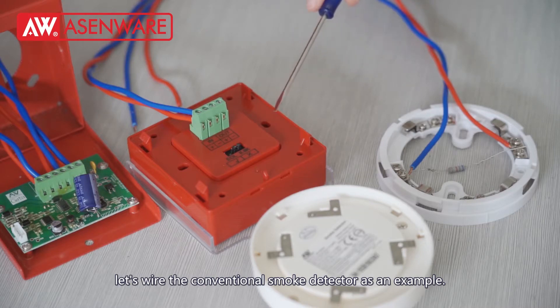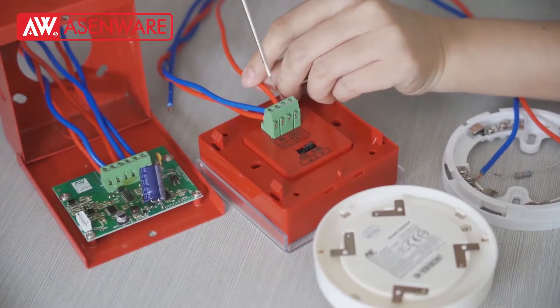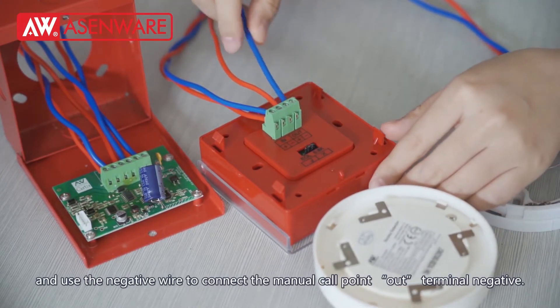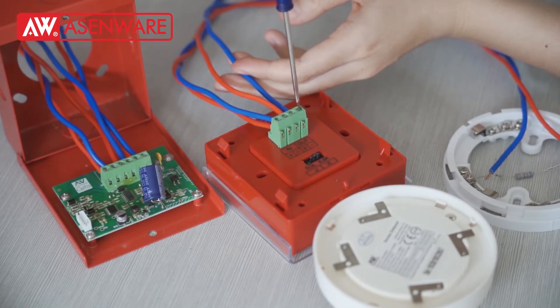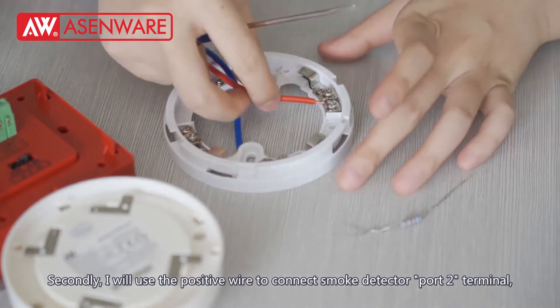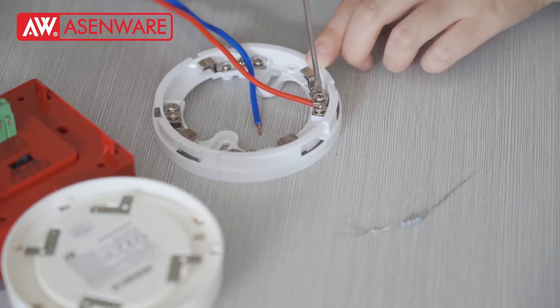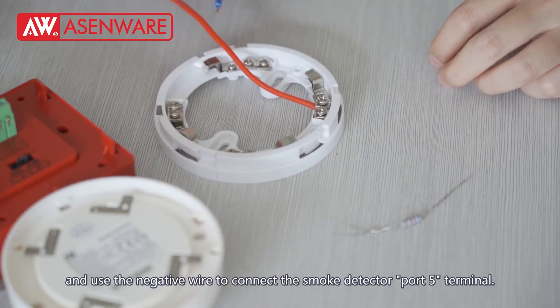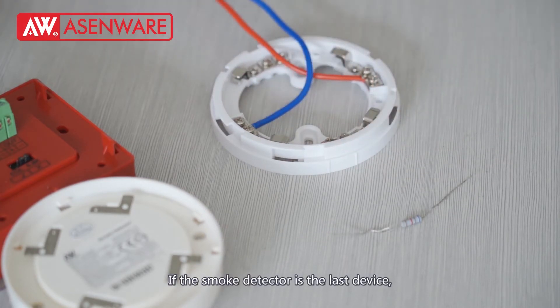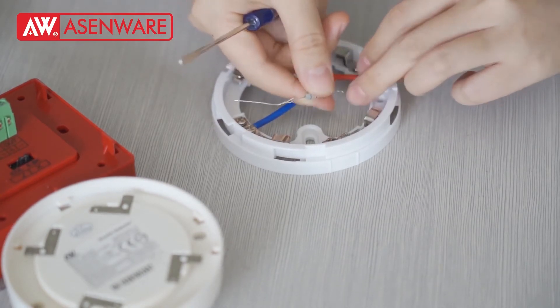Let's wire the conventional smoke detector as an example. Firstly, I will use the positive wire to connect the manual call point out terminal positive, and use the negative wire to connect the manual call point out terminal negative. Secondly, I will use the positive wire to connect the smoke detector port 2 terminal. If the smoke detector is the last device, we need to add the resistor on port 2 and port 5 terminal.